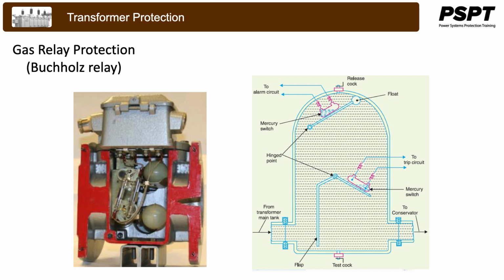The Buchholz relay usually has two elements that monitor: first, gas accumulation, made up of a float and some kind of position-activated switch—in this case, a mercury switch, which in more eco-friendly designs today could be a reed relay acted upon by a moving magnet. The second element measures gas pressure change, made up of a moving diaphragm and again some kind of position-activated switch, either a mercury switch or a reed relay. For simplicity, let's assume the mercury switch is used in both cases.